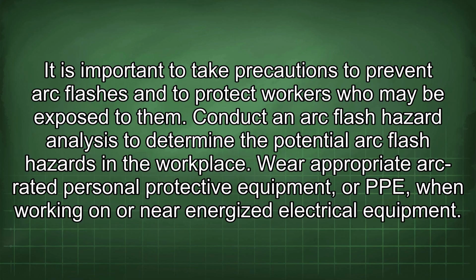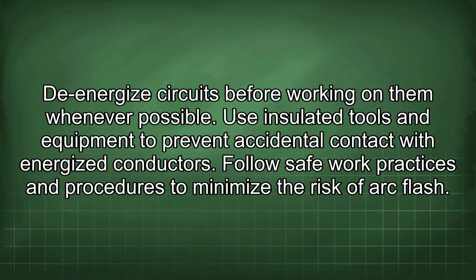Conduct an arc flash hazard analysis to determine the potential arc flash hazards in the workplace. Wear appropriate arc-rated personal protective equipment, or PPE, when working on or near energized electrical equipment. De-energize circuits before working on them whenever possible. Use insulated tools and equipment to prevent accidental contact with energized conductors. Follow safe work practices and procedures to minimize the risk of arc flash.